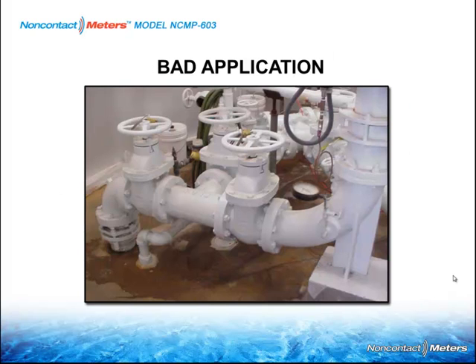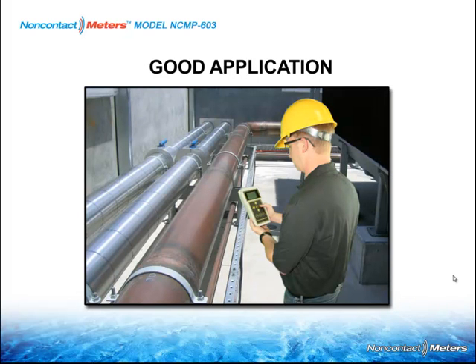As far as applications, it always happens. You get in your car and you drive 100 miles to go do a flow survey, and this is the application you find. And there's no straight run of pipe, and the customer says, hey, I just want to see it read. Well, if you want to just show it read wrong, then you'd put it here. It wouldn't read anything. When you have a bad application, you have to walk away from the application or put the bottom line in. You've got to have enough straight run of pipe. So you may have to go before, you may have to go after this application, upstream, downstream, and somebody may actually have to pull out a backhoe to get this device to work properly.